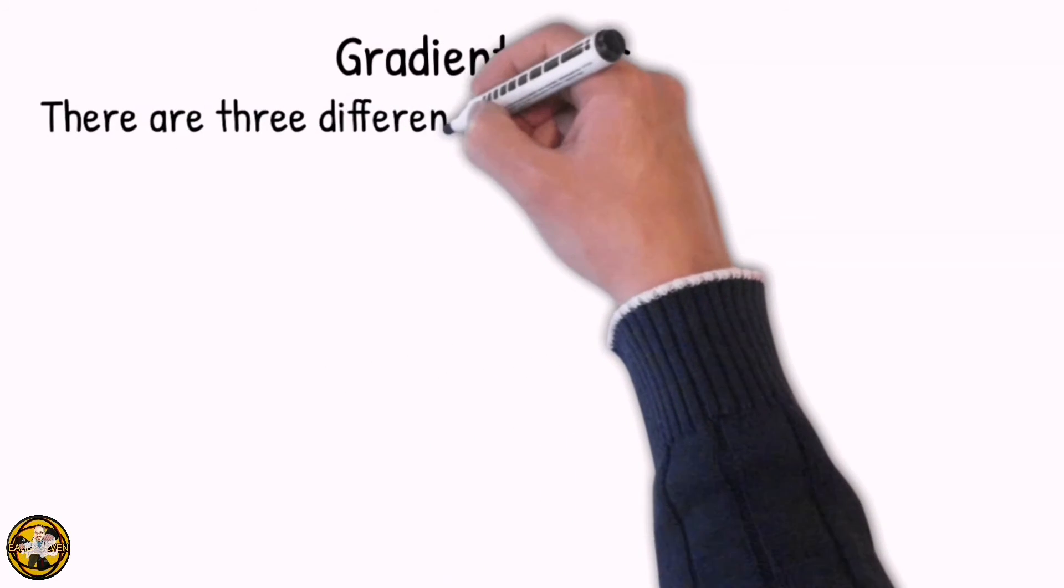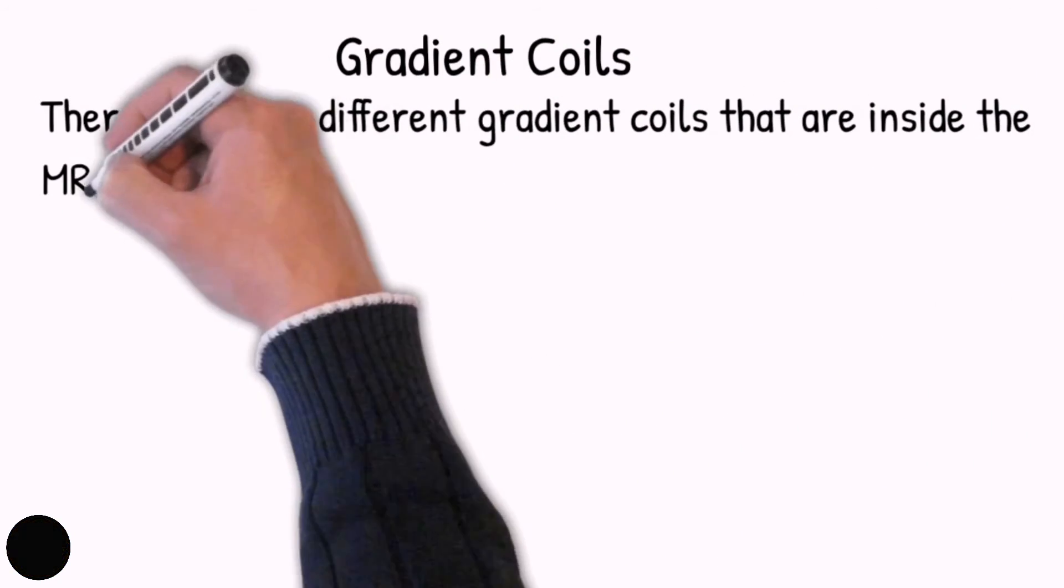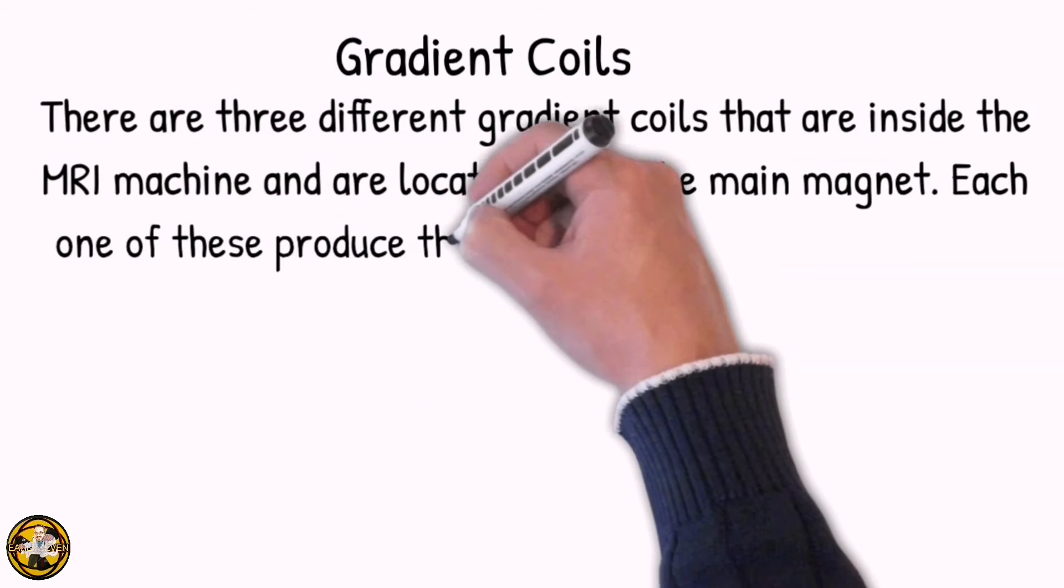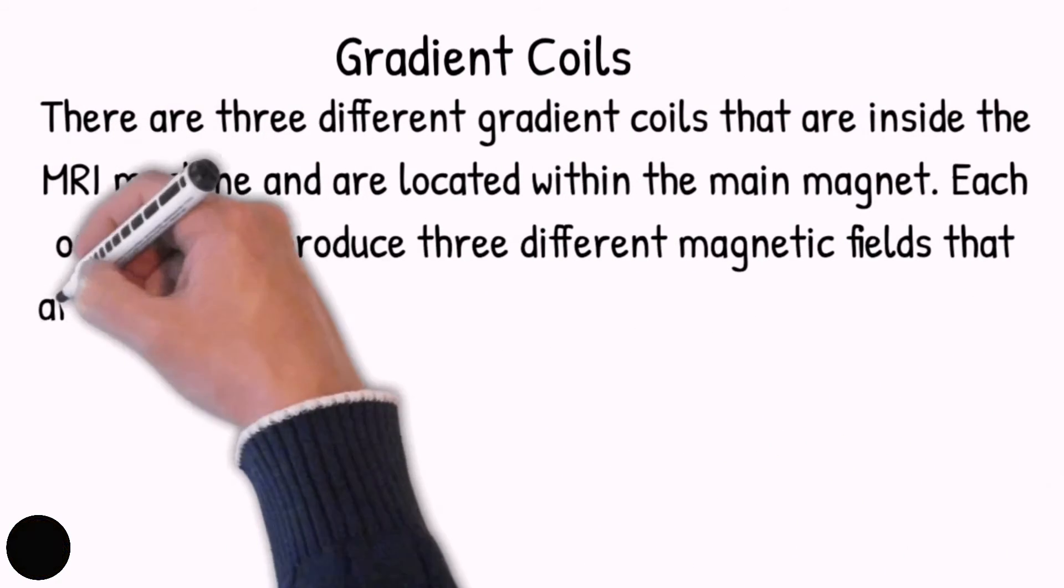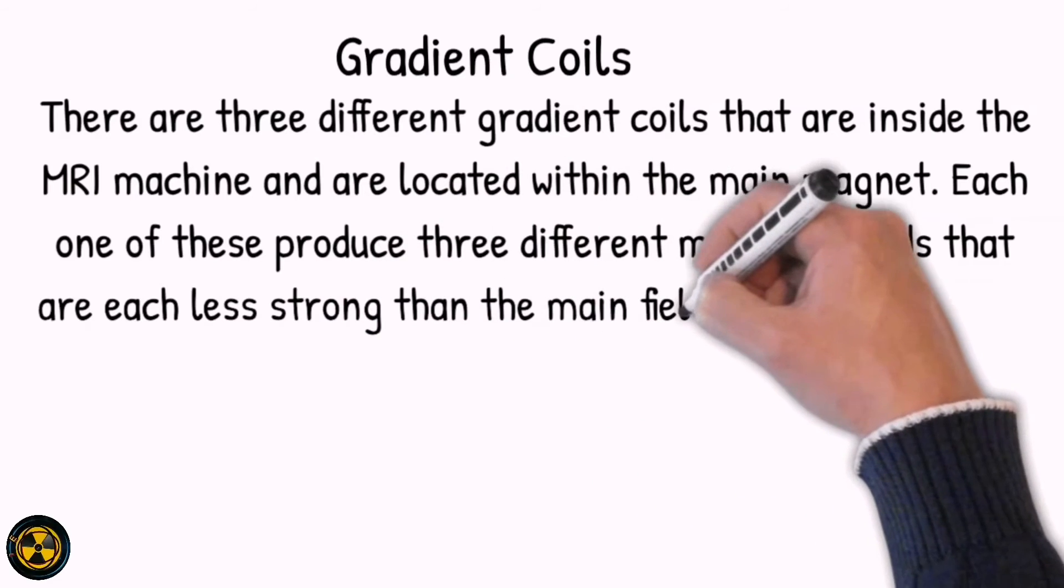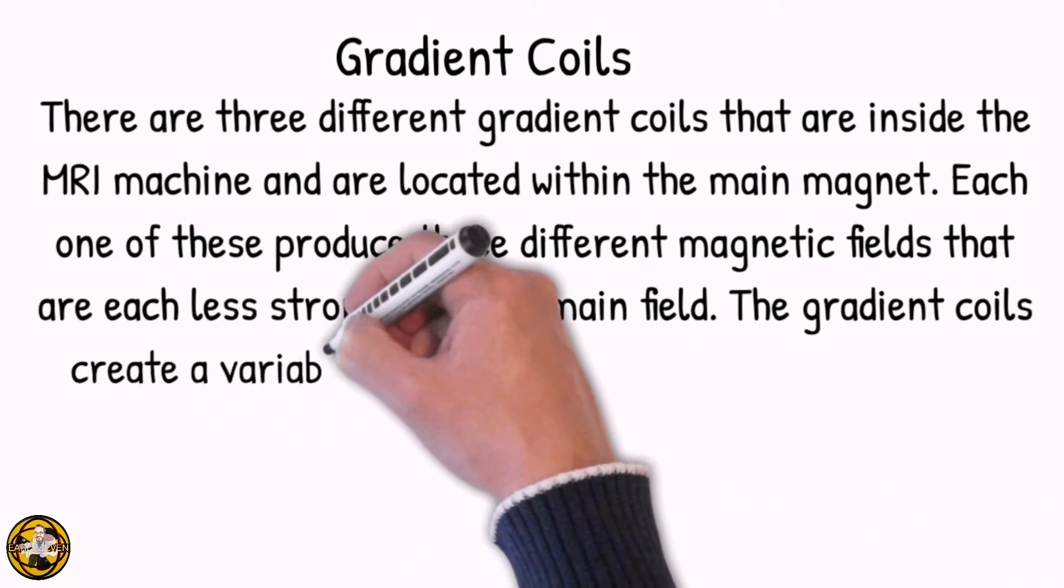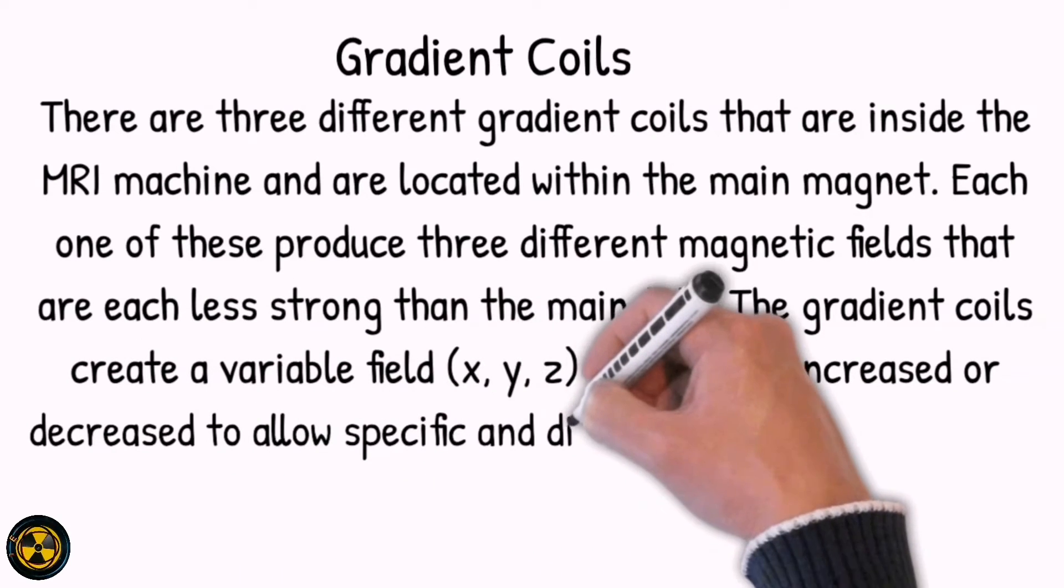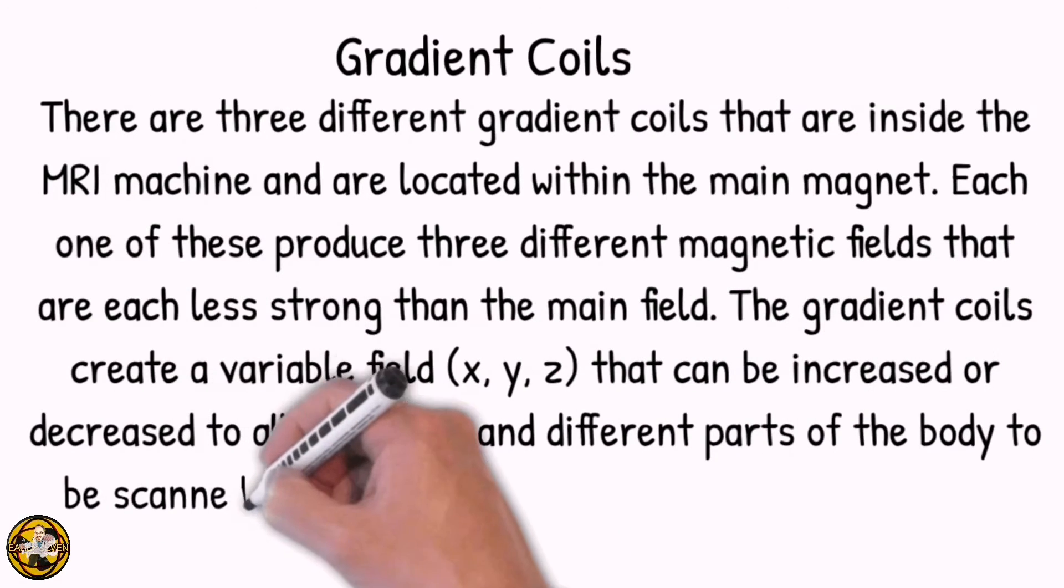The second component is the gradient coils. There are three different gradient coils that are inside the MRI machine and are located within the main magnet. Each one of these produces three different magnetic fields that are each less strong than the main field. The gradient coils create a variable field of X, Y, and Z that can be increased or decreased to allow specific and different parts of the body to be scanned by altering and adjusting the main magnetic field.